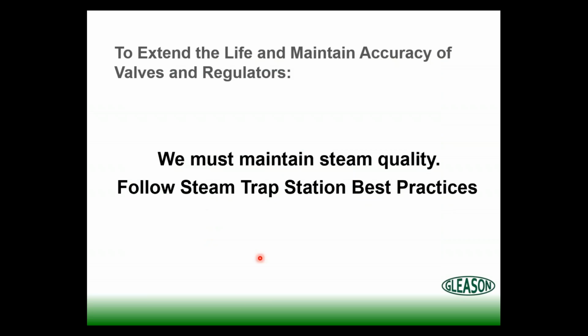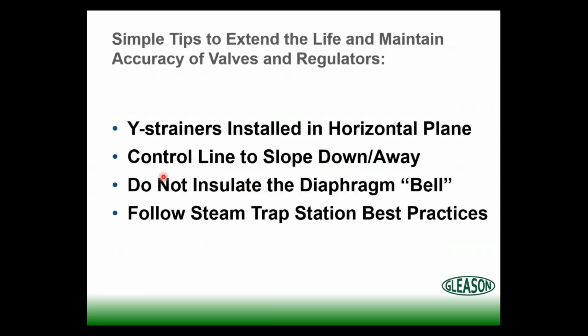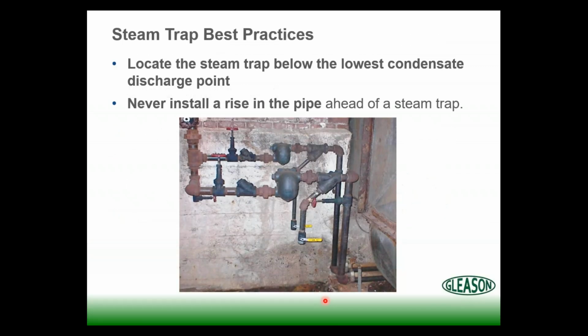So we've got to maintain your steam quality. We've got to follow our steam trap station best practices we talked about earlier. Let's install our Y strainers in the horizontal plane. Let's slope that control line down and away from the pilot. We don't insulate the bell on the regulators. And then lastly, when we're talking about freezing, let's install the steam trap below the lowest part of what we're going to be trapping. Let's use gravity. I'd say 90 to 95% of all problems that we deal with in a steam system result from not evacuating the condensate. So let's just use common sense. Let's drop that trap down below the lowest point, and that way those coils aren't going to freeze, among other things.